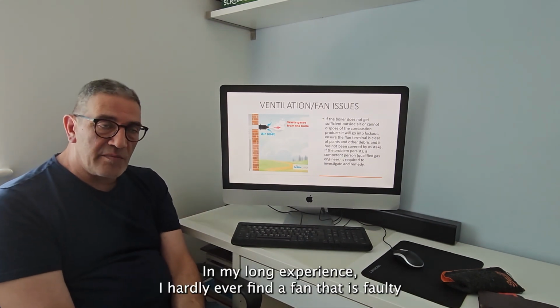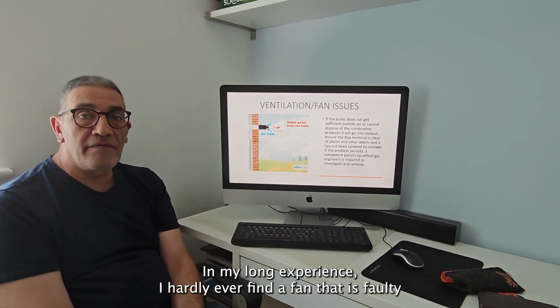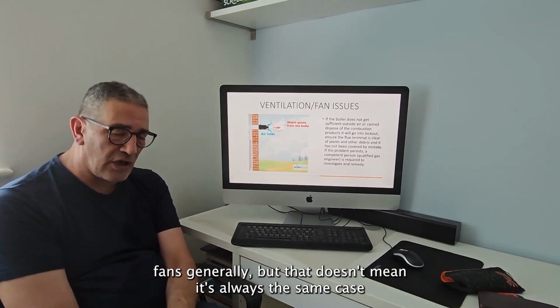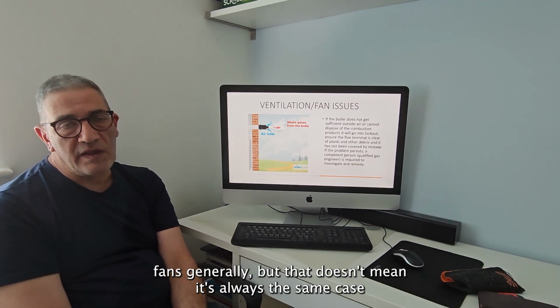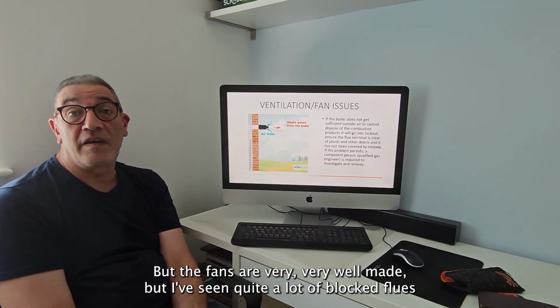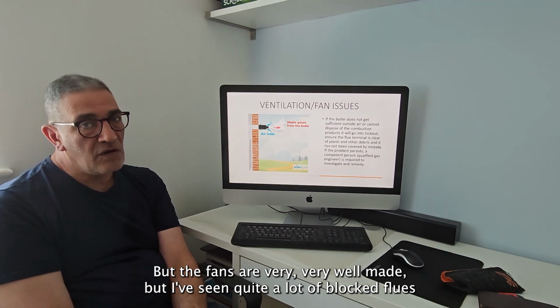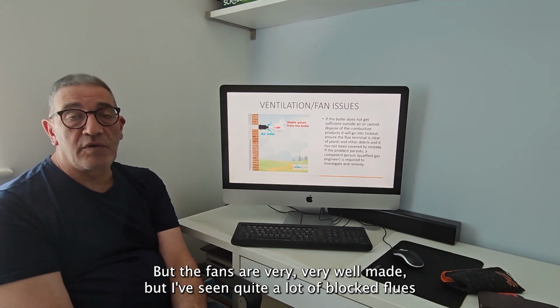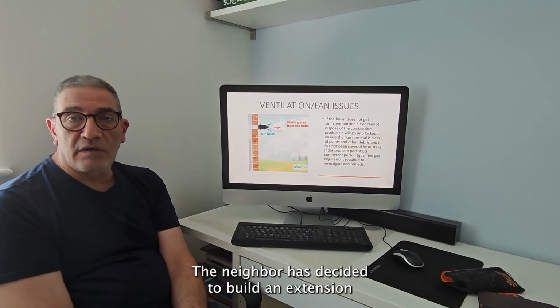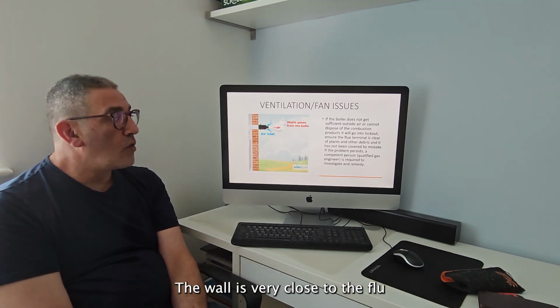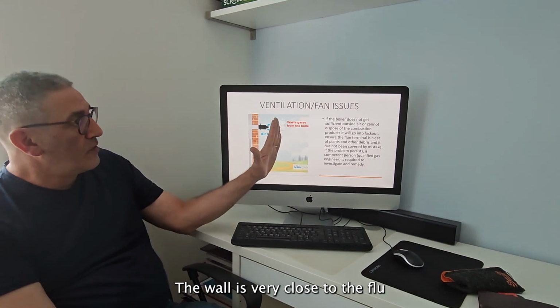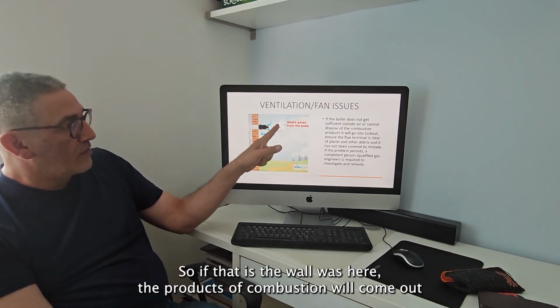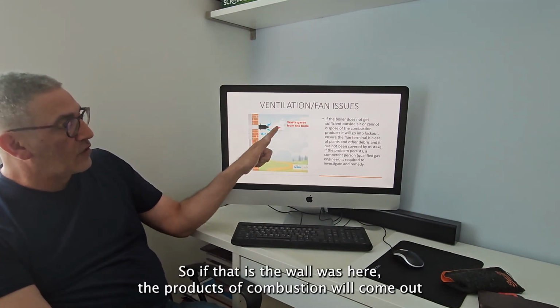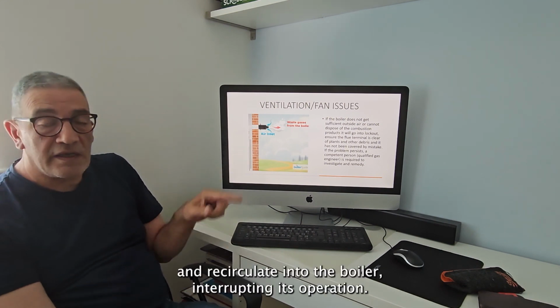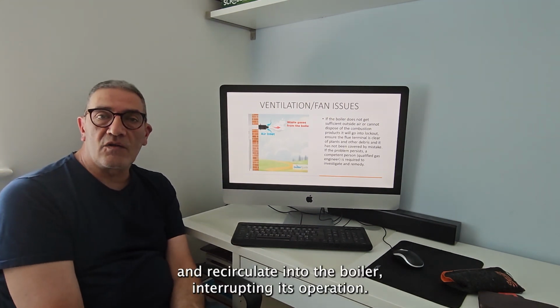In my long experience, I hardly ever find a fan that is faulty. That doesn't mean it's always the same case, but fans are generally very, very well made. But I've seen quite a lot of blocked flues. The neighbor has decided to build an extension. The wall is very close to the flue, so if the wall is here, the products of combustion will come out and will recirculate into the boiler, interrupting its operation.